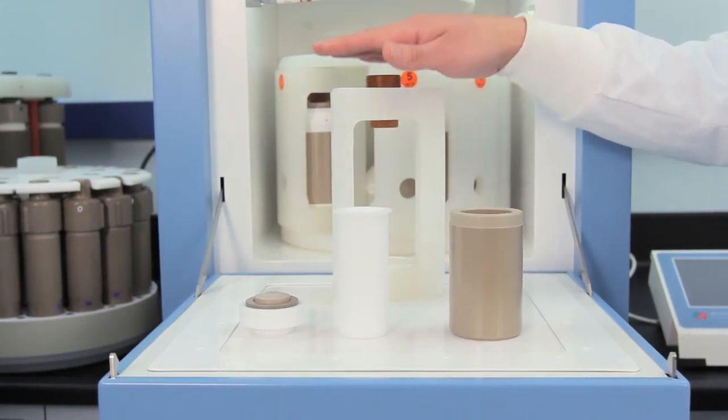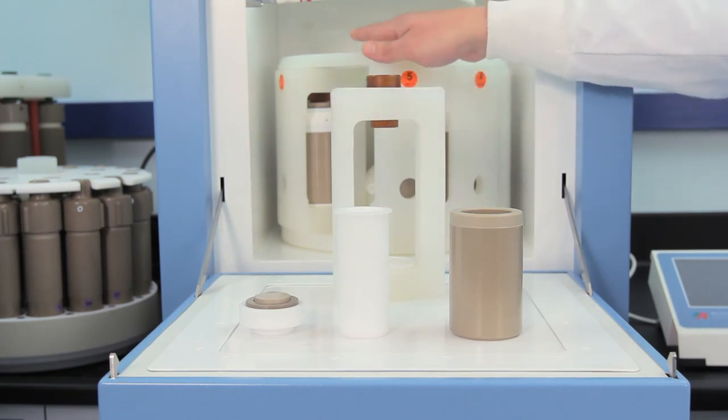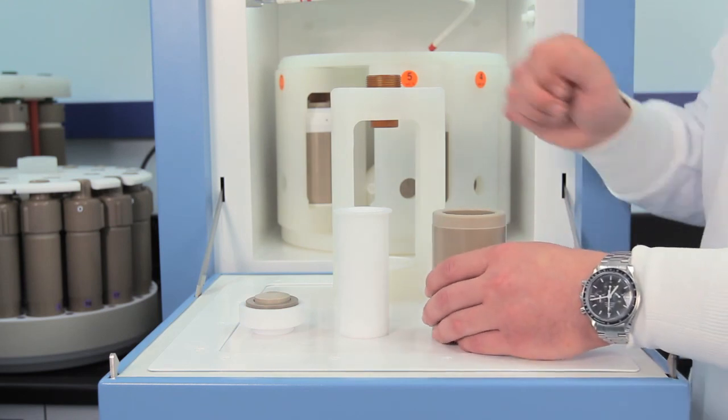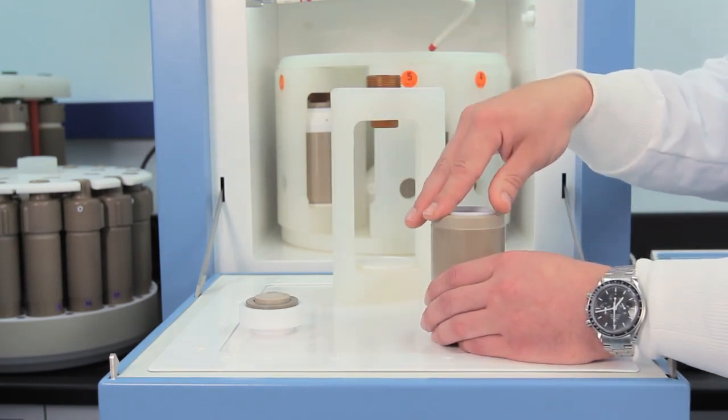This is the SK-10 high pressure rotor with 10 positions. It is a segmented rotor which means vessels can be loaded into the microwave individually if preferred. The vessel is capable of 100 bar of pressure and features Milestone's vent and reseal technology.